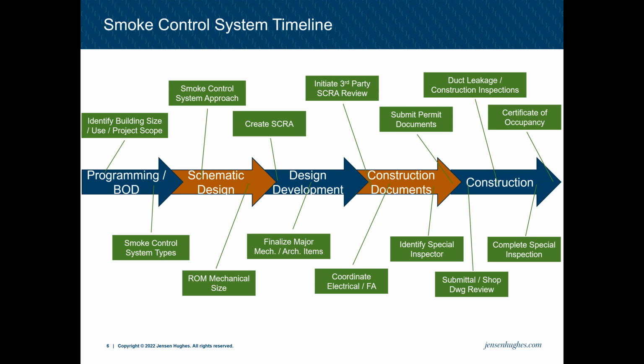Following the certificate of occupancy is obviously when the design is done and construction's done. But there are things to be aware of for smoke control, to make sure building owners and tenants are preparing for them. Namely, you have semi-annual and annual testing of smoke control systems, and making sure that owners are aware of that is very important.